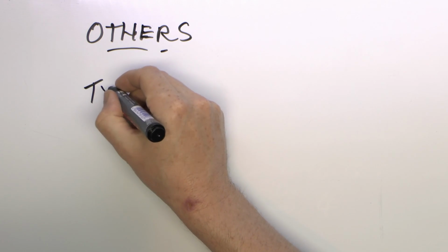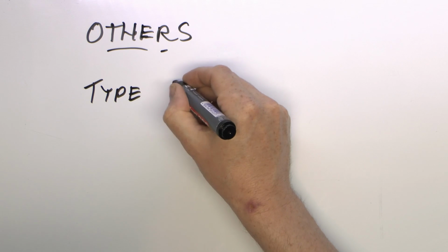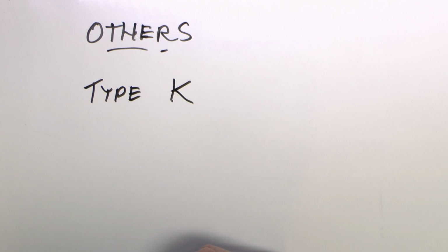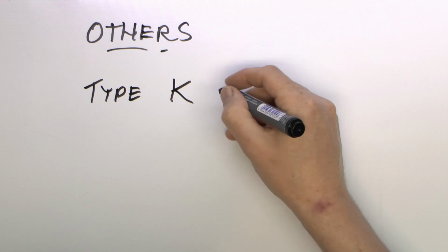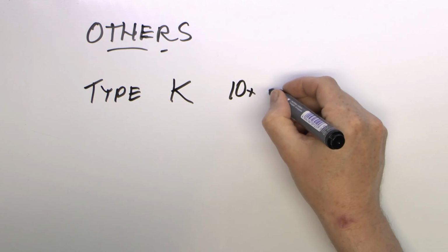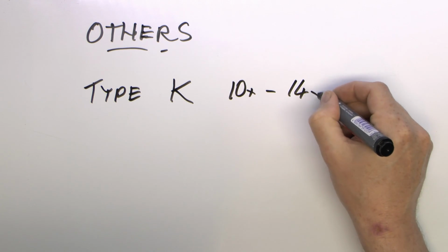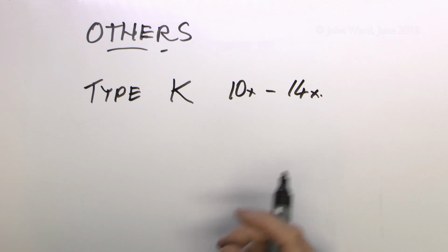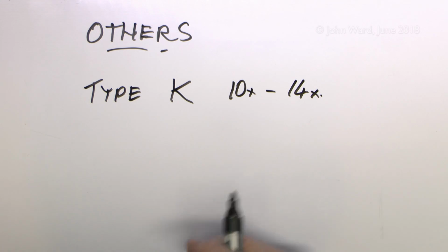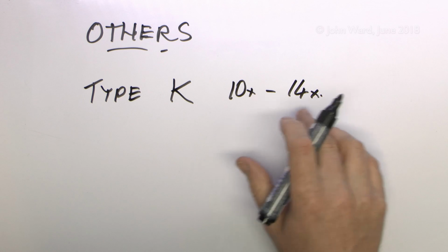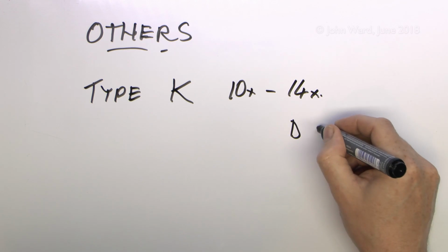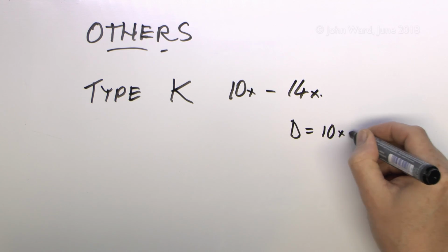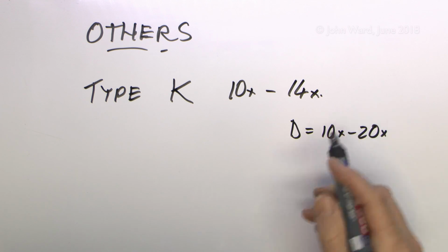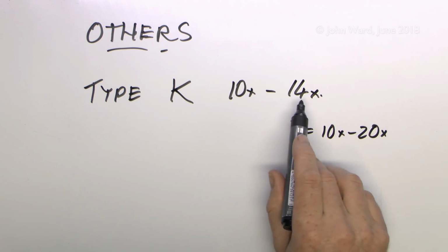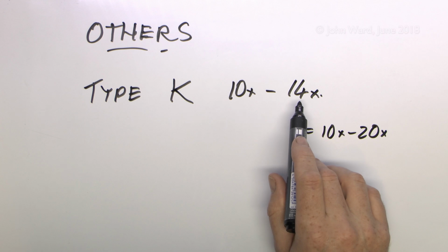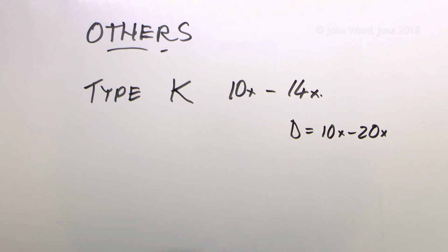So the first one of which is the Type K, and Type K will trip somewhere between 10 times and 14 times. So in that regard it's similar to the Type D, the only difference being that it's between 10 to 14, whereas the D was of course 10 to 20. So similar usage to the Type D. The difference is its upper level is considerably lower, so that may be useful in some applications.